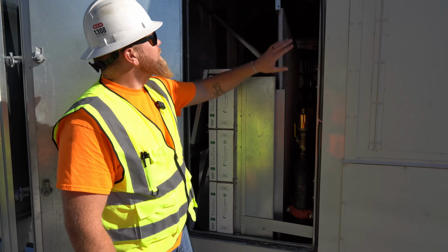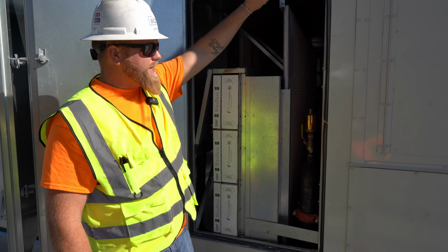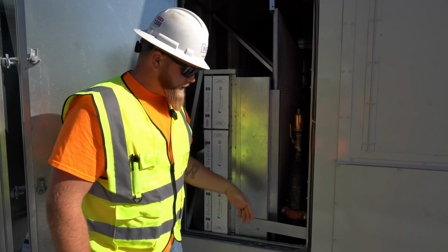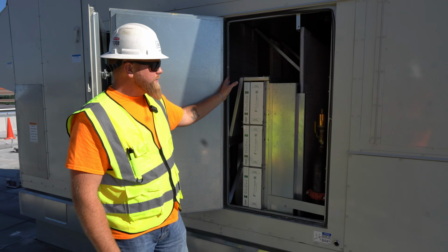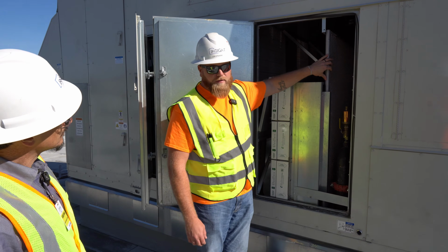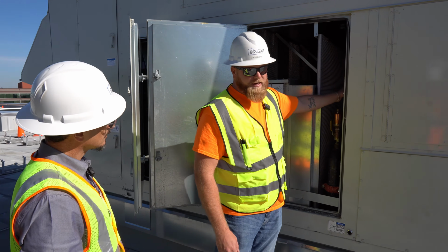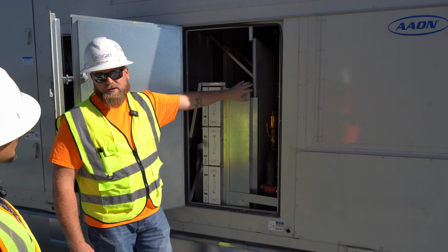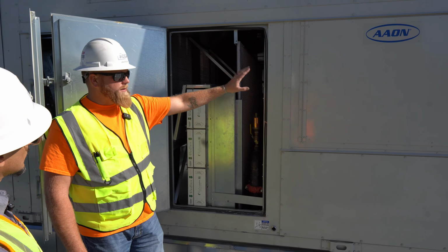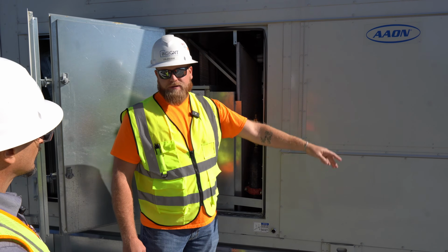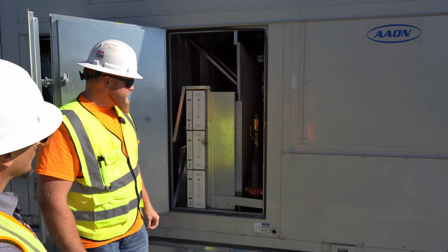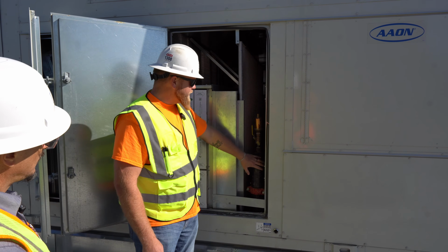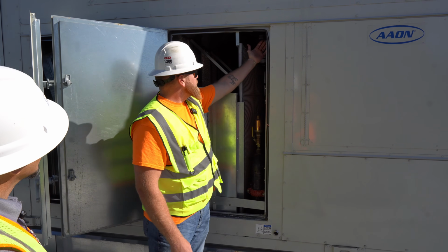So right here you'll have your condensing water loop coming up to the water-cooled condenser on the top of the system. As he just talked about, going through the 2 stages of cooling, you have your final reheat coil, and then we do a mixed air temperature reading to see what the discharge off the actual reheat coil is before any heat gain going down to the supply ducts of the system. That's nice. So this is just roughed in right now. This will be attached, these 2 attachments up here.